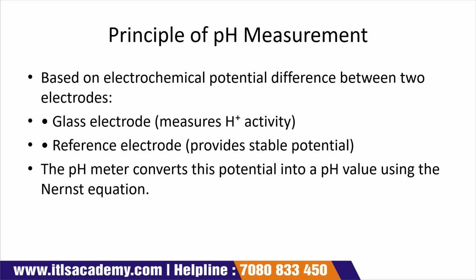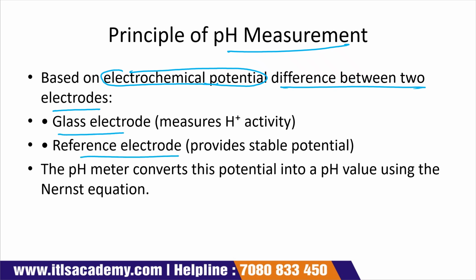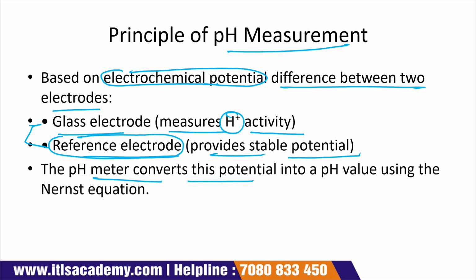Principle of pH measurement. pH measurement is based upon the electrochemical potential difference between two electrodes. We have a glass electrode and a reference electrode. So pH measurement is based upon the difference between these two electrodes and their electrochemical potential. The glass electrode is used to measure the hydrogen ion activity, and the reference electrode provides the stable potential. The pH meter converts this potential into the pH value by using the Nernst equation.